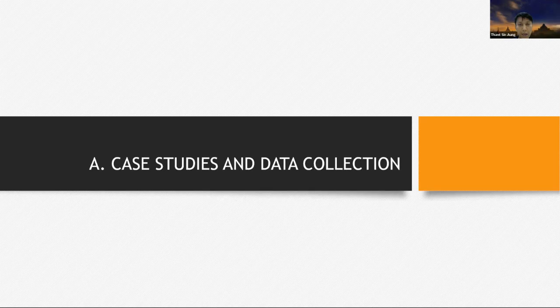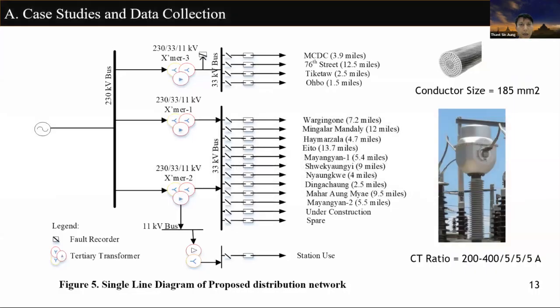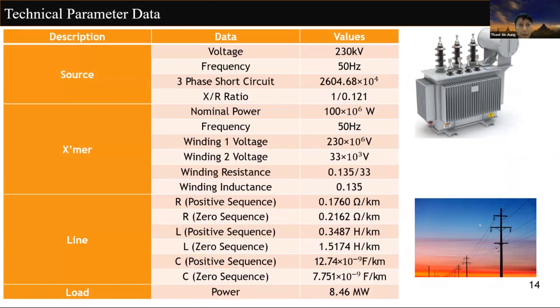It's for the case study and data collection. The case study is only for use in the Milbian distribution network. It's a 40 branch, 33 kV bus. It's transformed from 230 to 33 by using a step down transformer. The conductor size is 185 square millimeters, and the current transformer ratio is 200 to 400, and the secondary is 5 amperes. This is a technical parameter table for the source, transformer, line and load.